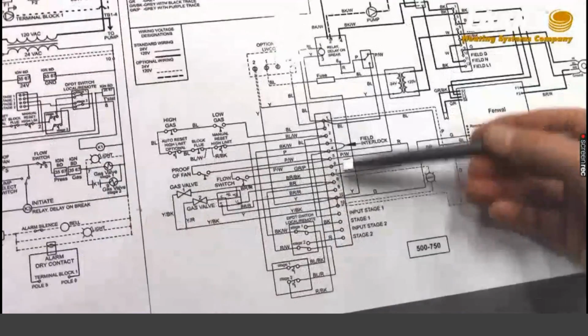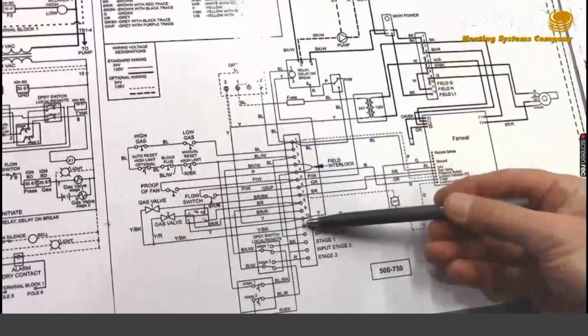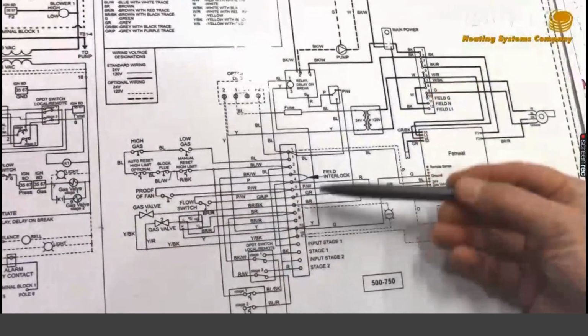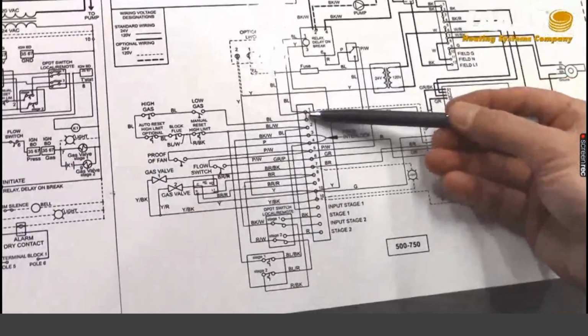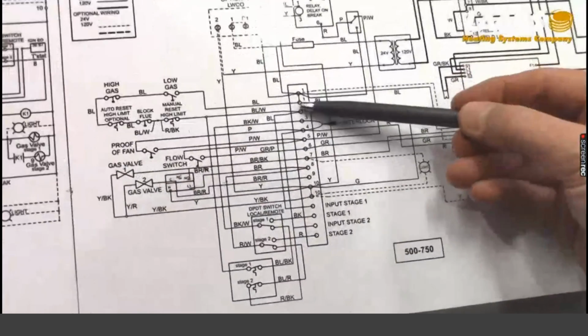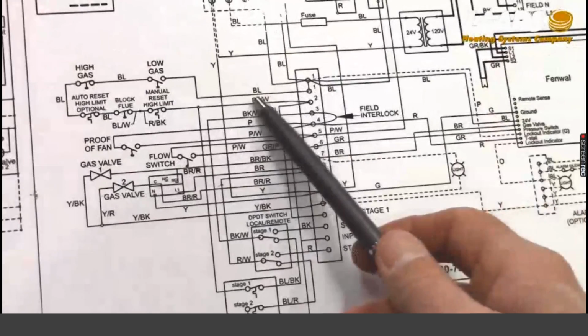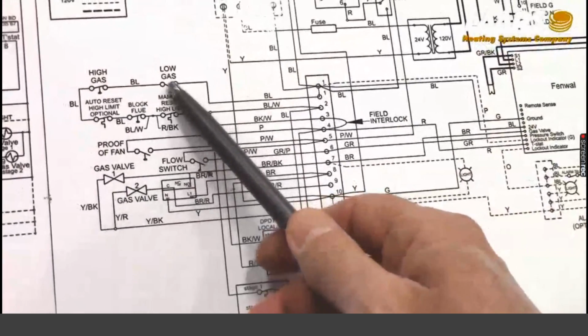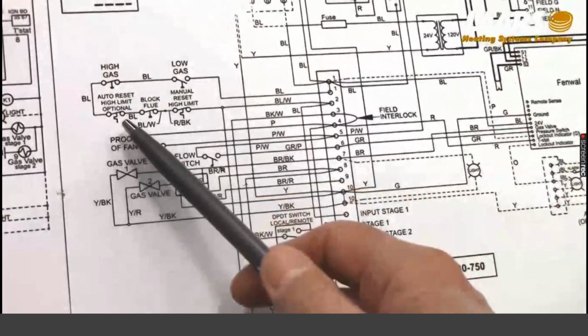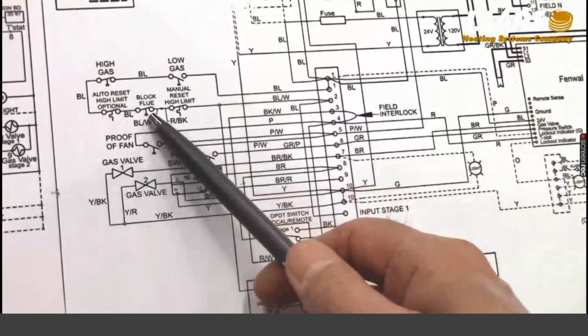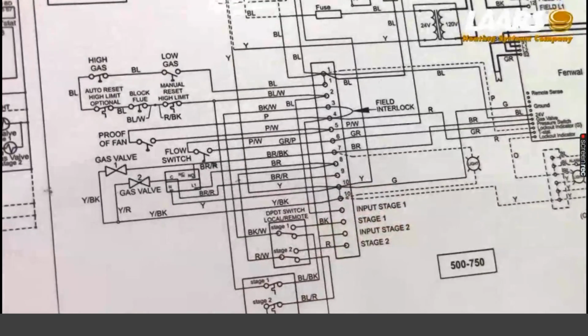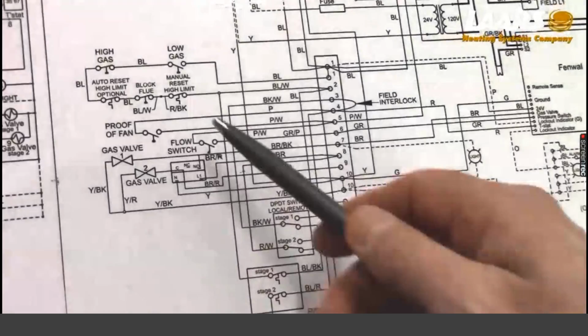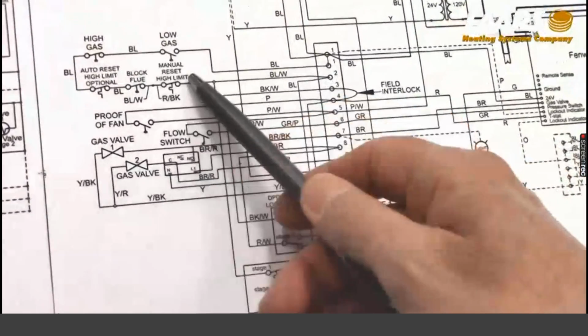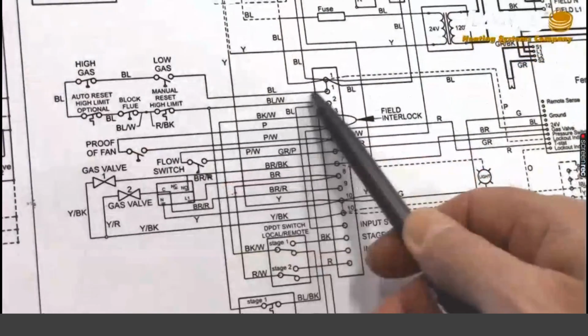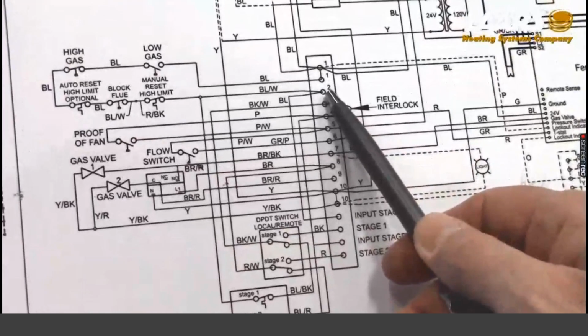Here are our terminal strips, okay. I mentioned number 10 is 24 volt common with the yellow wires. Terminal 1 brings power in, 1 and 1A. So that goes off to our low gas pressure switch, our high gas pressure switch, the limit, blocked flue, manual reset high limit. Okay, and then back to terminal 2. So what we have here was the open gas pressure switch to terminal 2, which I've just reset.